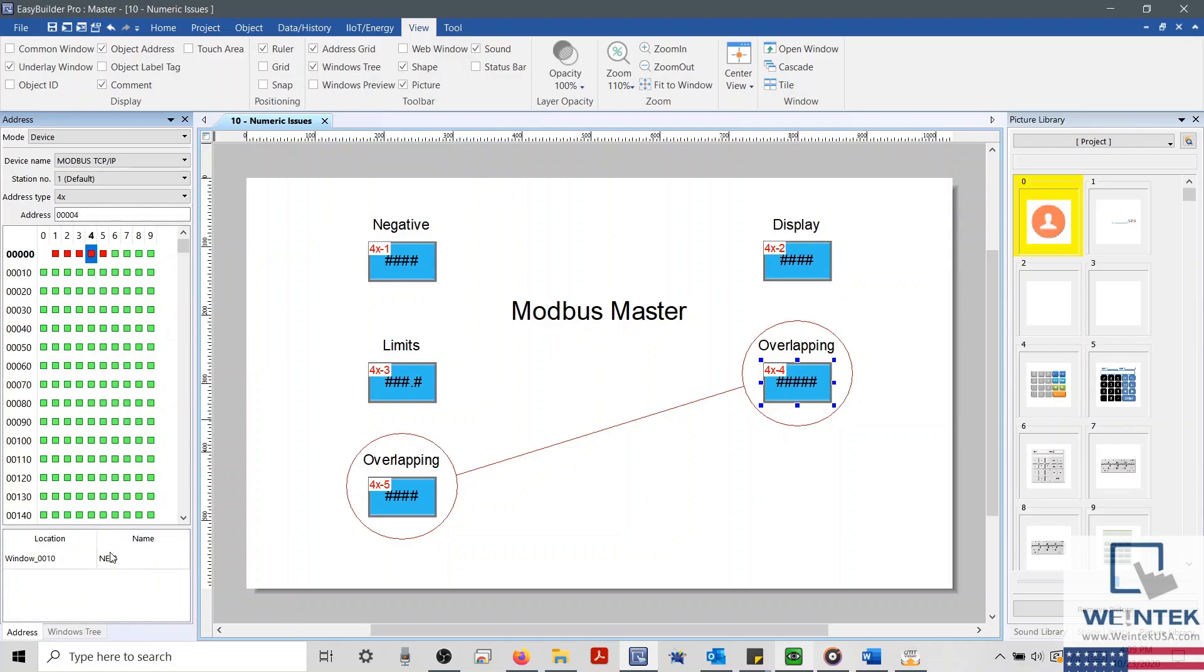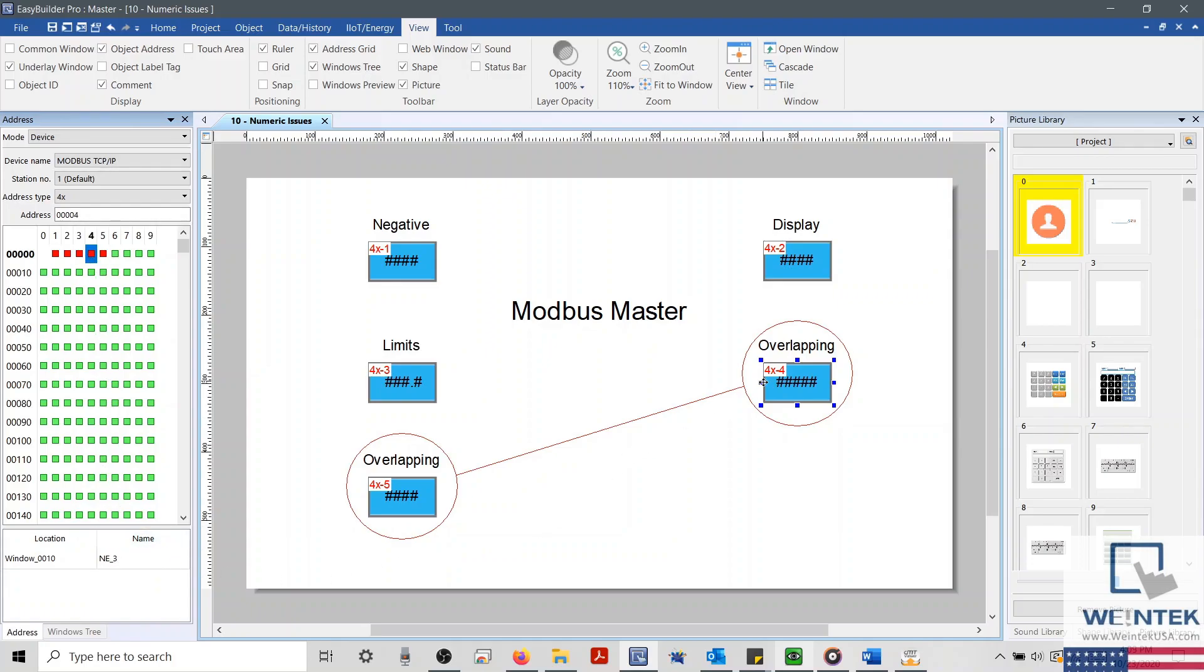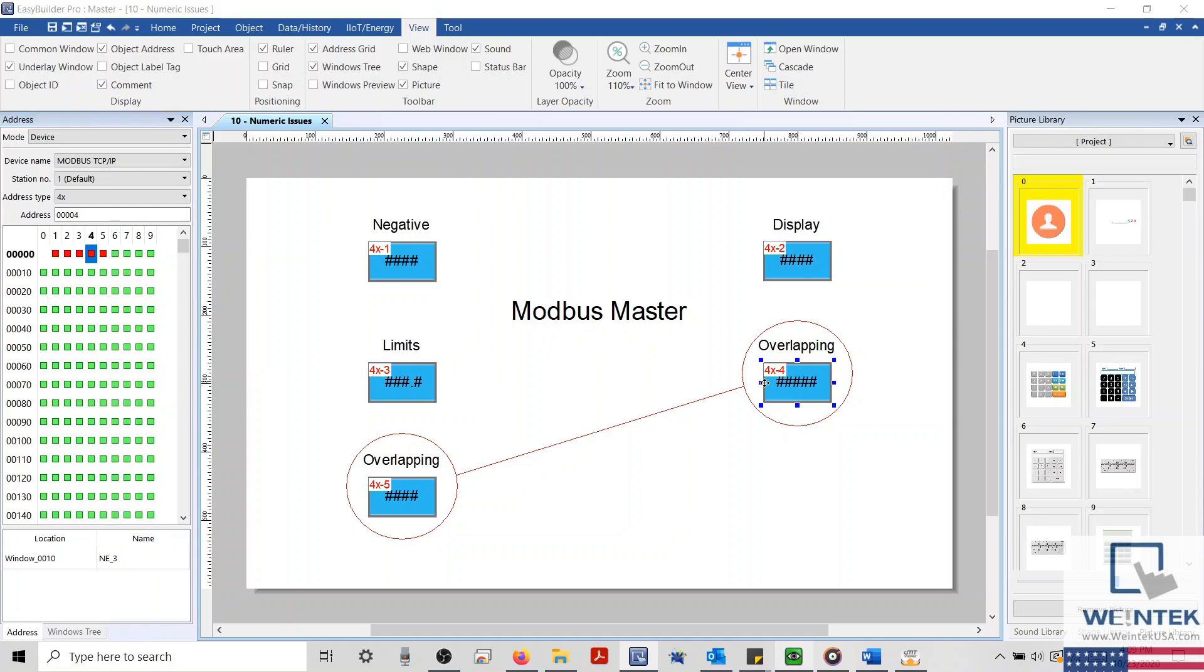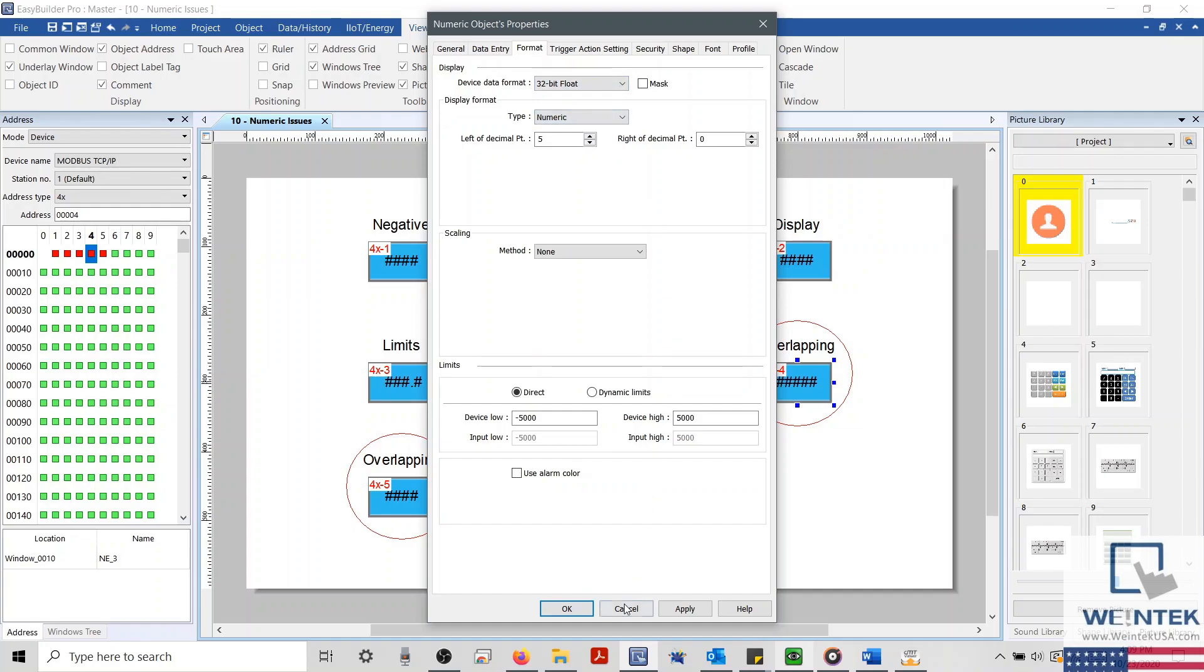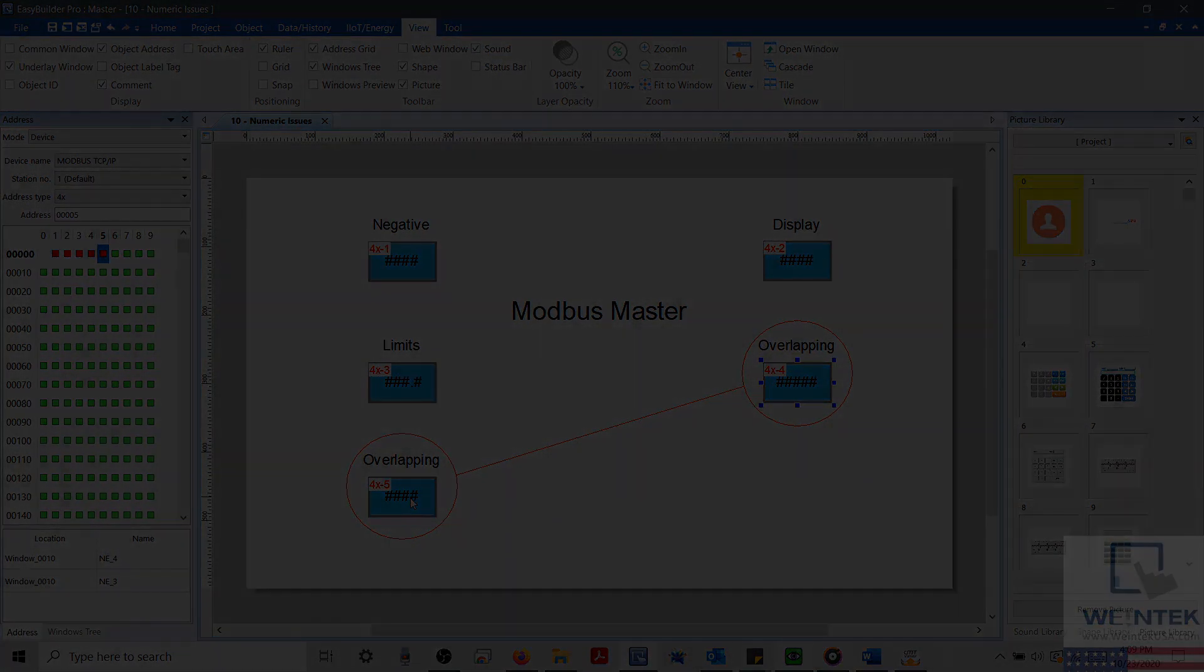When this occurs, we can tell that these objects are overlapping, meaning that our numeric object addressed to 4X4 has a 32-bit data format, which will consume two of our 16-bit address blocks within our address grid. To correct this, we will need to remap either our 4X4 or 4X5 object to a different register to prevent overlapping.